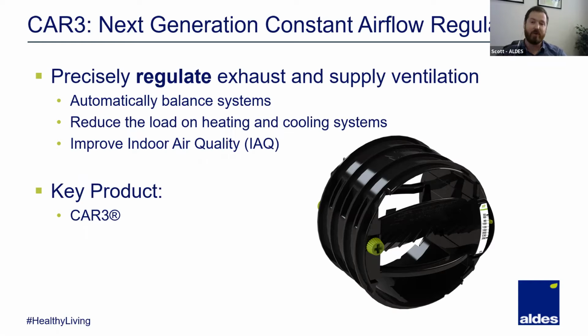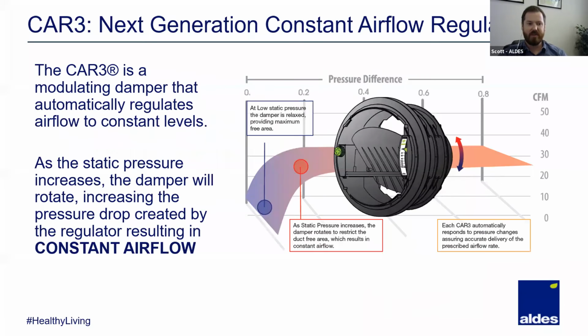And it's not just in regards to smells and odors and things like that. It's CO2, it's humidity, it's airborne illnesses, which are the things that a lot of people like to talk about these days. By reducing contaminant movement, you're going to have better indoor air quality. And by controlling and making sure that you maintain your correct ventilation rates, you're going to have good indoor air quality. And we do all of that with the CAR3, right? So the key product in this application and in all of our assemblies that are in the airflow and zone controls product range for Aldes, they're all based on the CAR3. So once you understand how the CAR3 works, then everything else will be very easy.